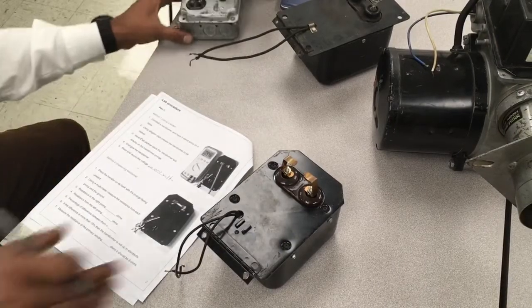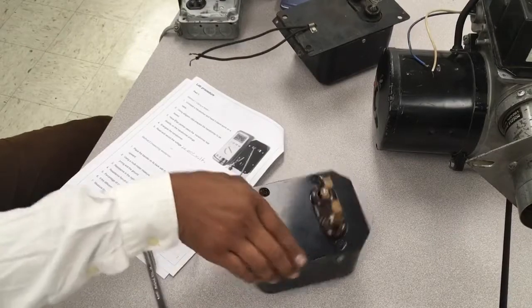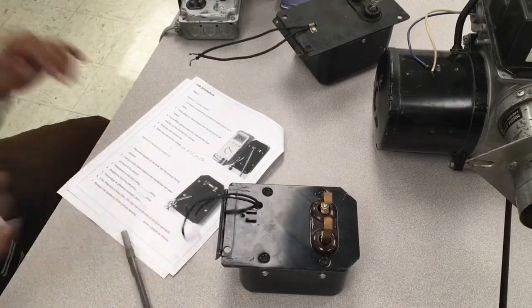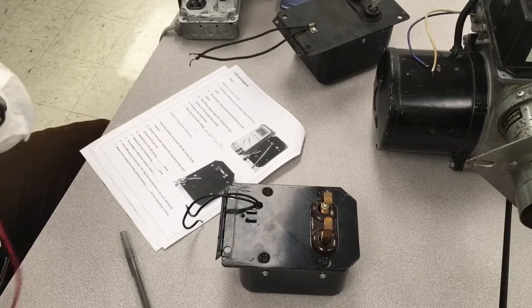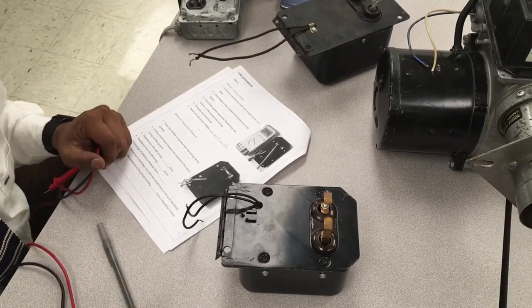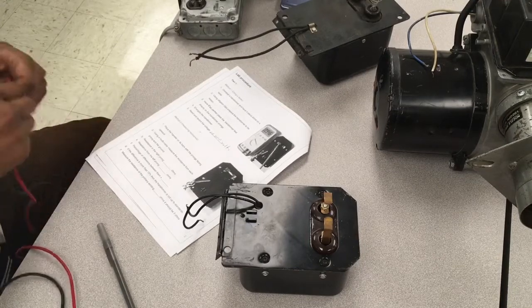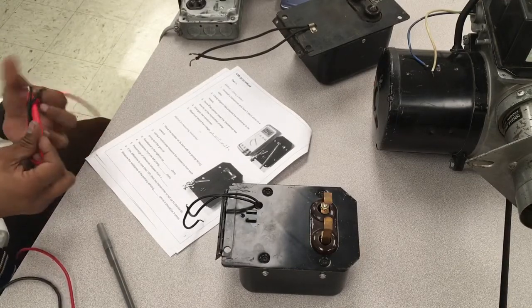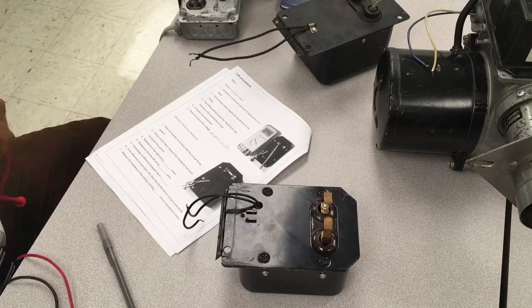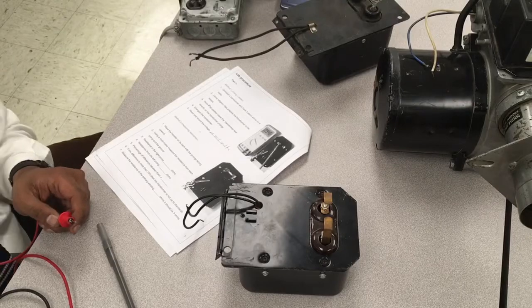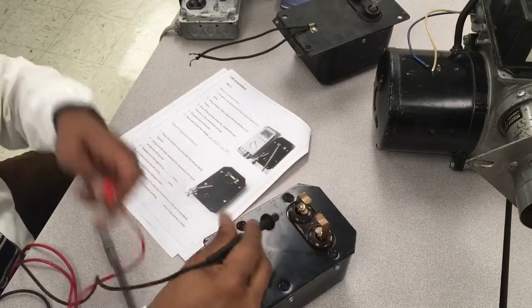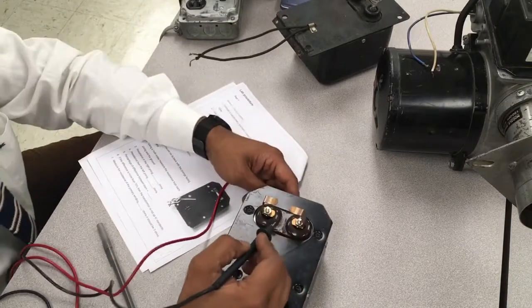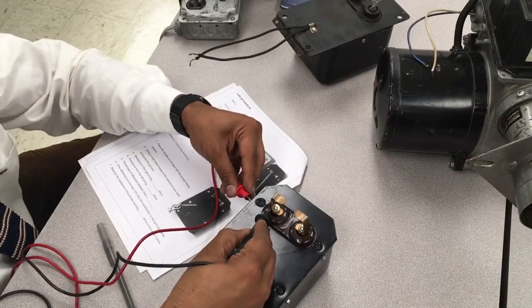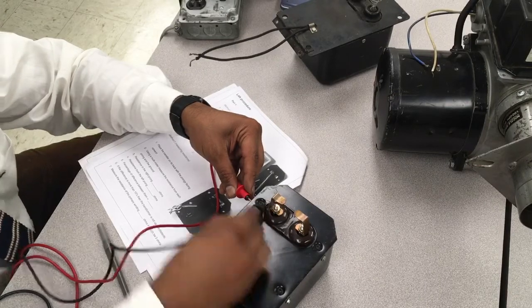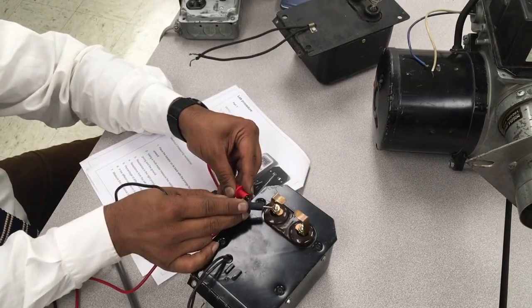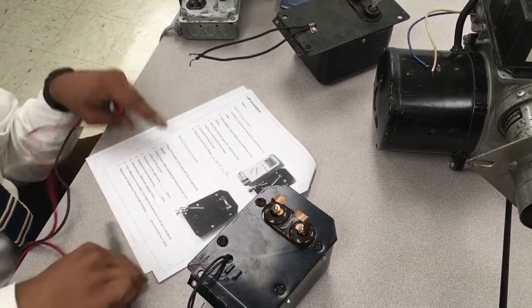Okay, so method 2: you place the transformer disconnected. You don't need any energy for that, and we will use our multimeter on the resistance reading, the ohm meter. Using the multimeter, measure the resistance from each prong. These are the prongs, so we'll measure the resistance from this prong to any casing. Usually they have a ground in here, so I measure the resistance from here, and it's showing, as you can see, 11.82, and you will record that.